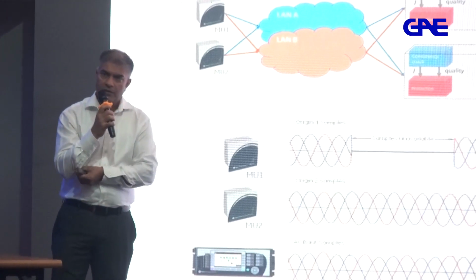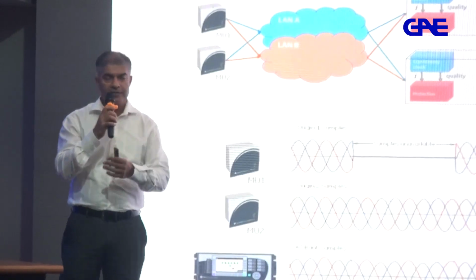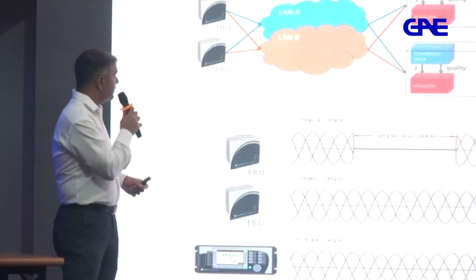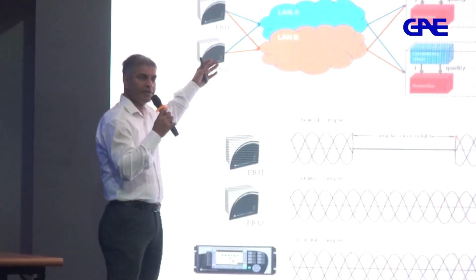In your design, if you have, let's say, main 1, main 2, completely duplicate, so distance 1, distance 2, and these 2 relays are connected to 2 different merging units, okay? The principle is that if you have failure of one merging unit, you have the second set. So if system A fails, you have system B as an alternative. That's fine. What if you are using main and backup protection? If you don't have duplicate protection as system A, system B, or X and Y, and you have main and backup, some designs have distance as a main protection function, and let's say directional overcurrent as a backup protection function.